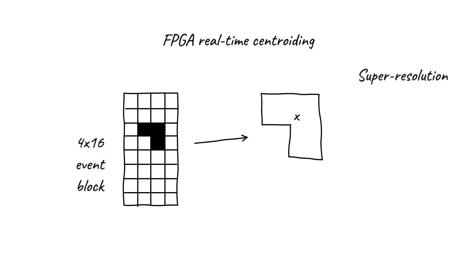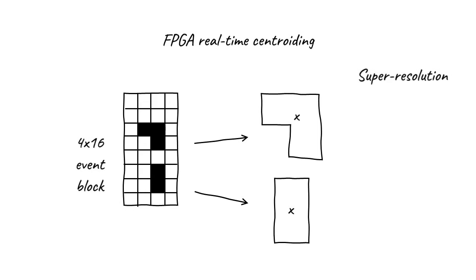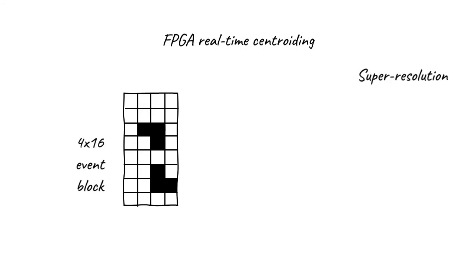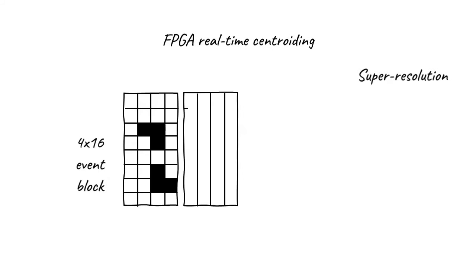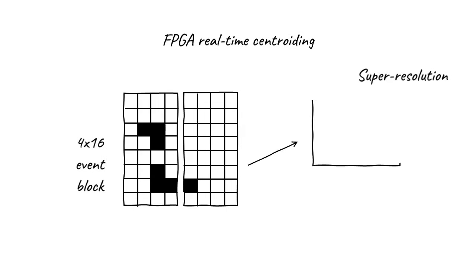You may wonder what would happen if an event block contains multiple distinct detection events. In this case, the FPGA distinguishes these two events as separate, and centroids each event separately. Finally, what happens if a detection event spreads across the boundary between event blocks? When the FPGA sees a detection event on the boundary of an event block, it also looks at the adjacent event block to see if the detection event spreads across. If so, the event is stitched together and centroided correctly.